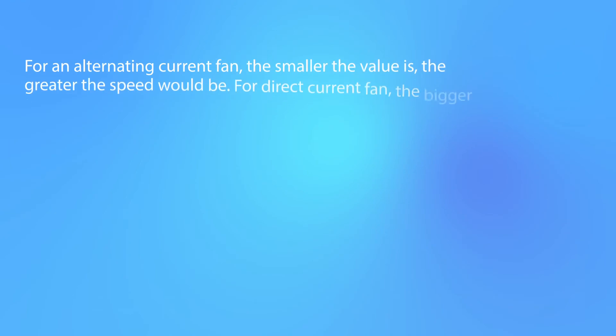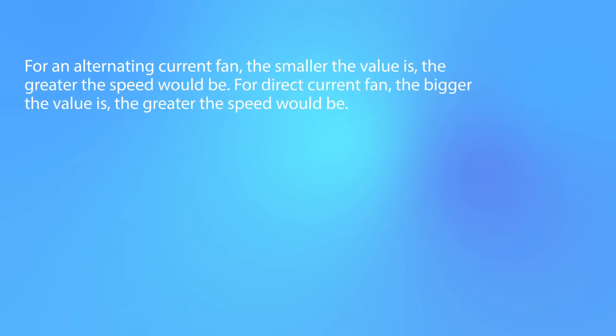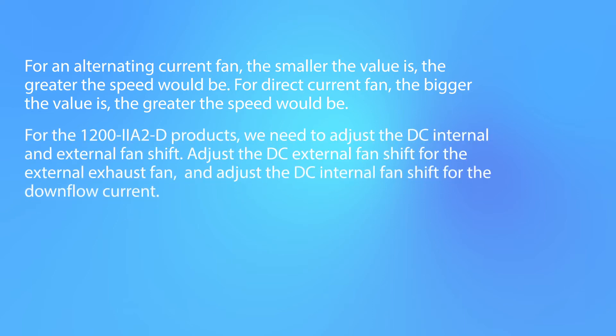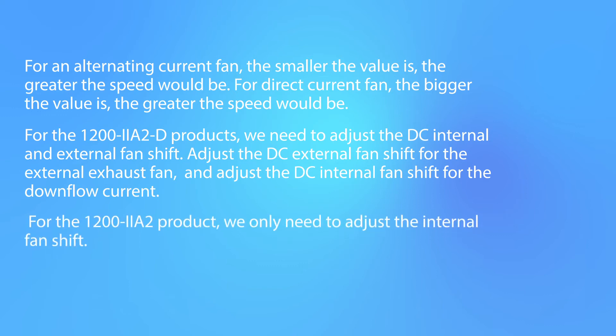For an alternating current fan, the smaller the value is, the greater the speed would be. For a direct current fan, the bigger the value is, the greater the speed would be. For the 1200-IIA2-D products, we need to adjust both the DC internal and external fan shift. Adjust the DC external fan shift for the external exhaust fan, and adjust the DC internal fan shift for the downflow current. For the 1200-IIA2 product, we only need to adjust the internal fan shift.